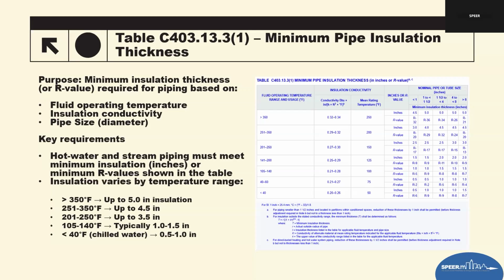High temperatures and larger pipe diameters naturally require more insulation. For piping carrying fluids above 350, the insulation requirement is typically 5 inches regardless of pipe size. Temperatures between 250 and 350 require 3 inches to 4 inches or greater, depending on the pipe diameter. Anything over 350, it doesn't matter what size the pipe is. Mid-range temperatures: for water temperature between 105 and 200, the required thickness of the insulation is basically 1 to 2.5 inches. Most hydronic heating and service water heating systems fall into this category.